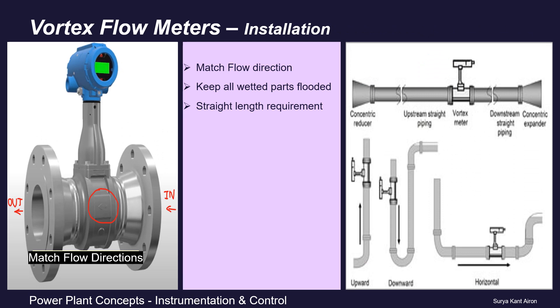For installation, first, similar to other flow meters, the flow direction marked on the meter must match the process flow direction. Second, all wetted parts must be kept flooded — vortex flow meters can be installed vertically, horizontally, or at any angle as long as they remain fully flooded for accurate measurement. Third, maintain at least the minimum manufacturer-recommended straight pipe length upstream and downstream of the flow meter to avoid flow turbulence from pumps, valves, bends, and tees.